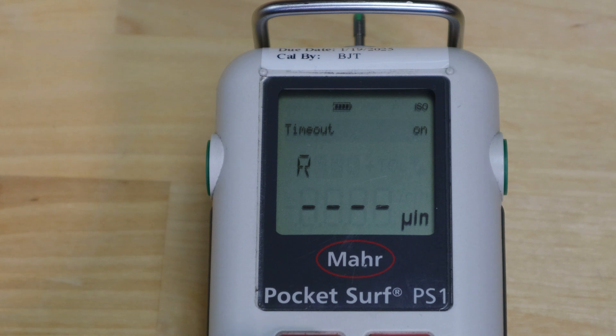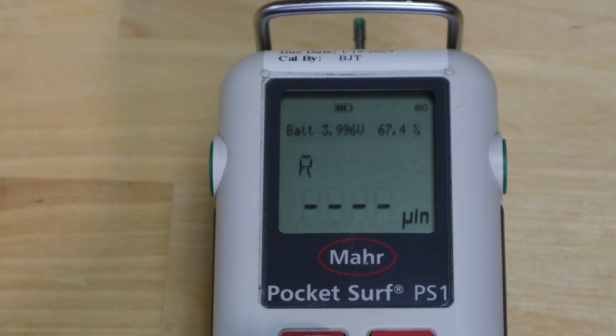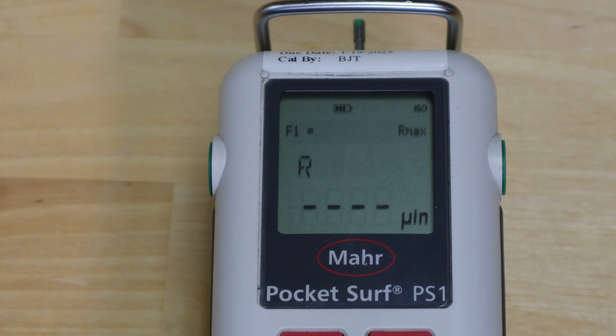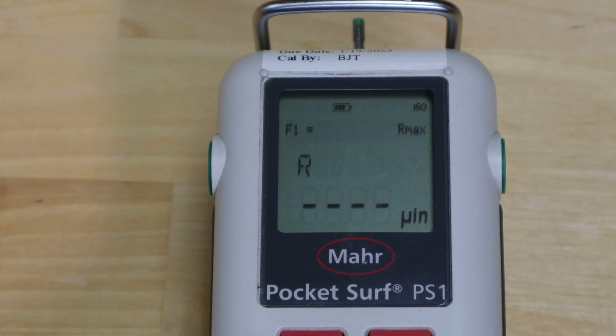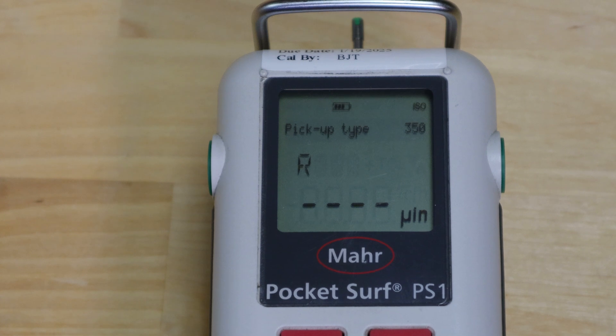You can also set timeout — how long before the screen turns off from inactivity to save battery power. Blocking lets you block unauthorized users by programming in your own code number. Battery power shows 67%. You can also program your F1 key — in this example it's set up for R max, but you could program it to output a different parameter. Pickup type refers to the stylus: this is a Mahr 350 style, and styli can be changed to longer, shorter, deep reach, or narrow reach options.